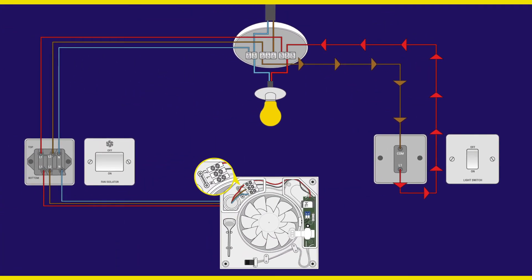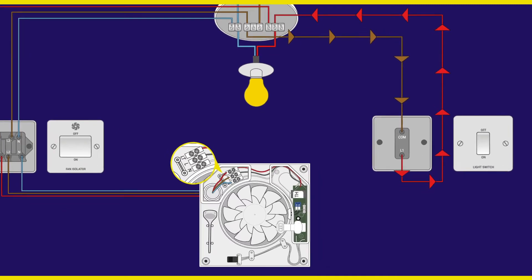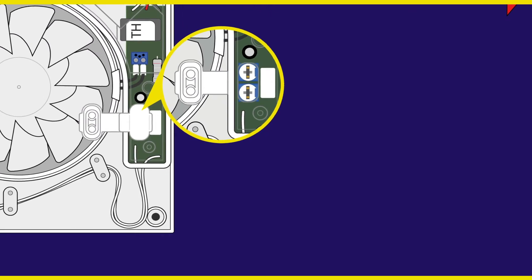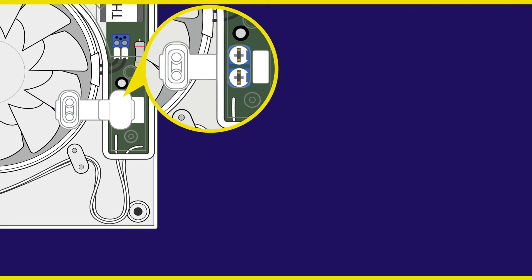However, when the switch is turned off, the fan will continue to run for a preset period of time. This is why we have the permanent live connection. Here you will see the small fan run on time adjuster.